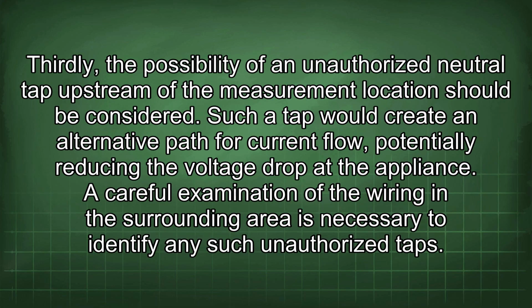Thirdly, the possibility of an unauthorized neutral tap upstream of the measurement location should be considered. Such a tap would create an alternative path for current flow, potentially reducing the voltage drop at the appliance. A careful examination of the wiring in the surrounding area is necessary to identify any such unauthorized taps.